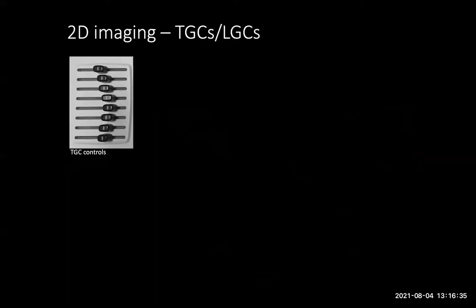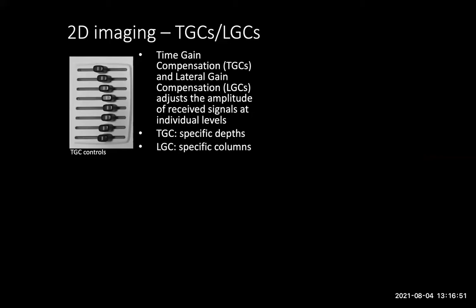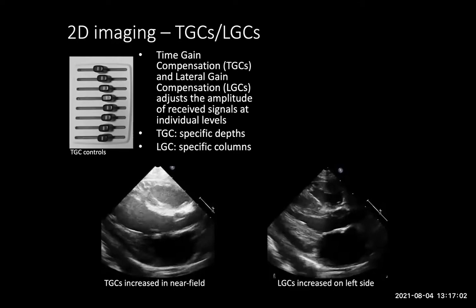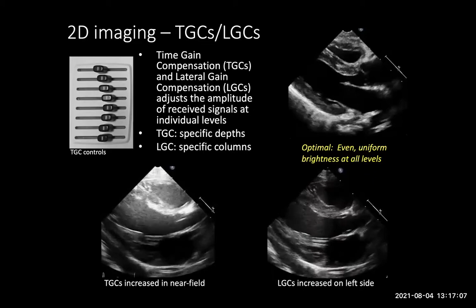TGCs and LGCs stands for time gain compensation and lateral gain compensation, which adjusts the brightness at individual levels. TGCs adjust gains at specific depths, whereas LGCs adjust gains at specific columns. Here, the TGC sliders have been increased in the near field, and we can see the brightness at the top of the image. In this image, the lateral gains have been increased on the left side of the sector. The goal is to have an image that is even and uniform, and adjusting the gains at different levels can help.